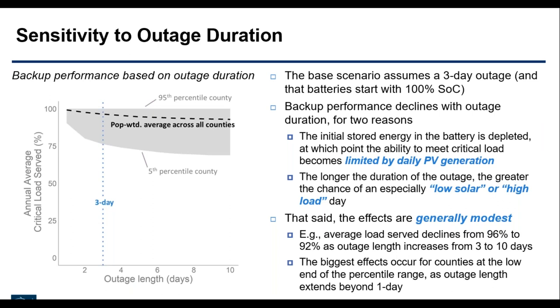What's interesting is that this doesn't move linearly as one might expect. As duration increases, backup starts declining for two main reasons. One is that the initial stored energy in the battery is depleted, and depending on conditions for PV production and net load, performance starts becoming limited by daily PV generation and net load. Again, we're making no assumptions here about demand response—we're just trying to meet this critical set of loads.